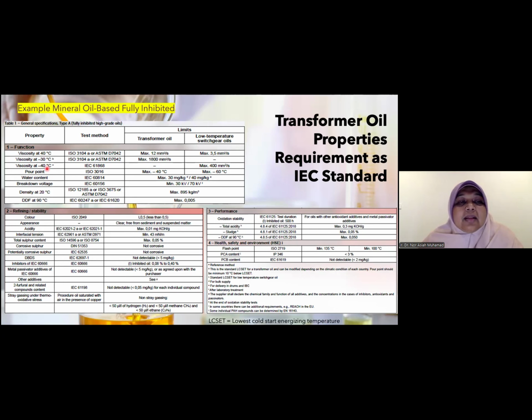The viscosity is a main important thing, because this oil also needs to act as a cooling medium, so it cannot be too viscous. Then the water content and breakdown voltage, this is a major one, the breakdown voltage. There are specific requirement limits. Water content matters because water inside electrical equipment at a certain point is very dangerous. It can be a conductor. So there are limits for water content.